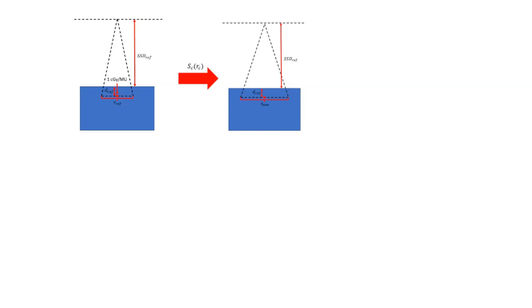Now I want to show what we're doing with one of these PDD calcs. So this is the reference condition here. This is what we established in TG51. We know that the accelerator is giving one centigray per monitor unit at this point at the reference depth, the reference field size, and the reference SSD. When we apply a collimator scatter factor, we are increasing that collimator field size and accounting for the difference in dose to the calculation point because of changing that jaw size. And that's the step shown here.